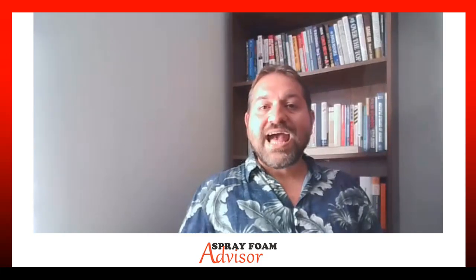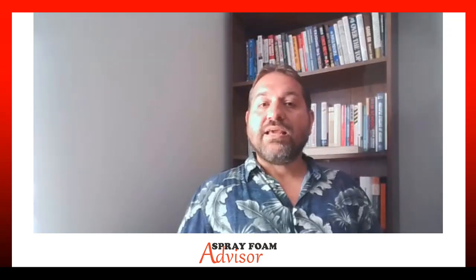We have a traditional attic with a gas combustion water heater in the space. You are asked to come into the project and create a closed, unvented attic using spray foam insulation in the retrofit project. What happens next?